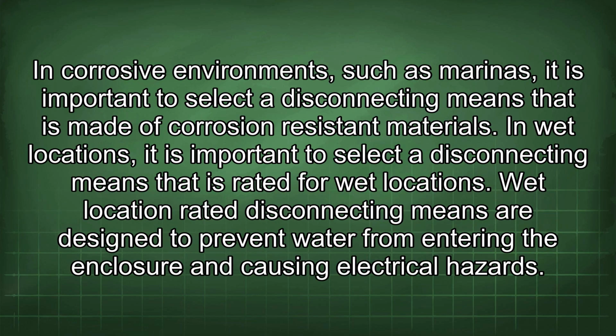In corrosive environments such as marinas, it is important to select a disconnecting means that is made of corrosion-resistant materials. In wet locations, it is important to select a disconnecting means that is rated for wet locations. Wet location rated disconnecting means are designed to prevent water from entering the enclosure and causing electrical hazards.